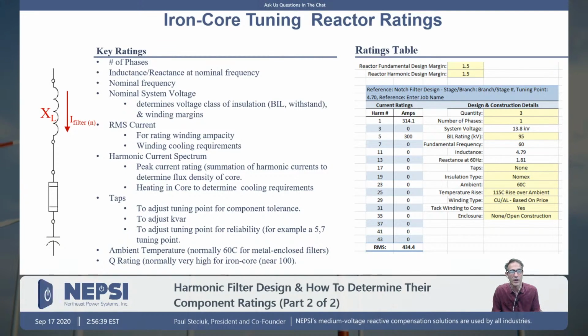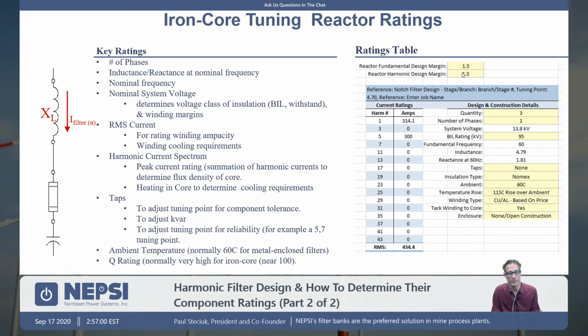And then the temperature rise really is dependent upon the insulation level. Is it a 220 C insulation system or a 150 C insulation system? For us, we oftentimes go to a 220 C insulation system, so we would specify a 115 degree C rise. One key thing I'm pointing out here is we have some margins up here. Very often, and I would recommend that you think about this, your fundamental current rating of the reactor should be specified at 1.5 times the actual current that we'll see during operation.